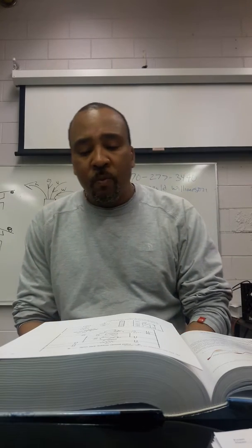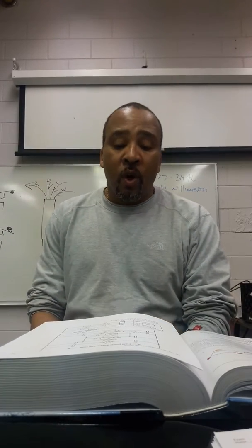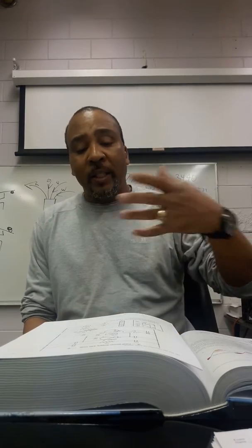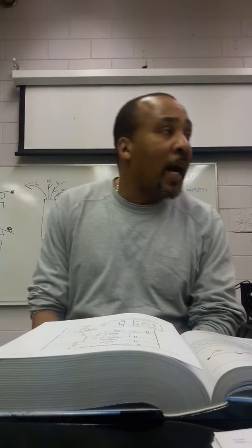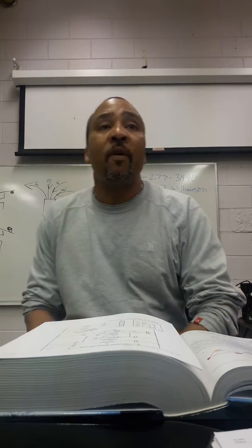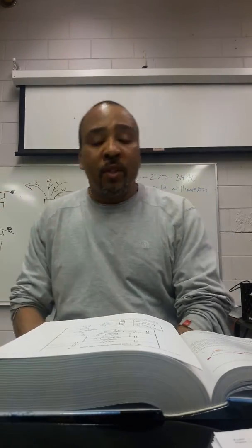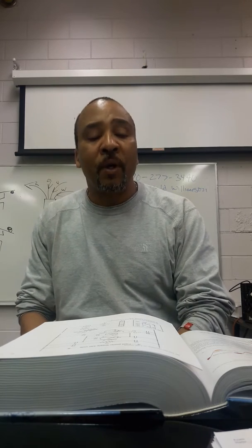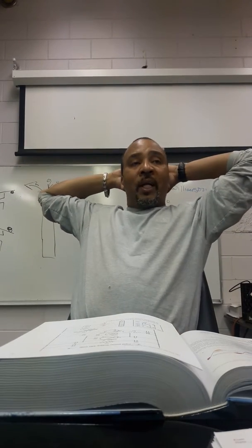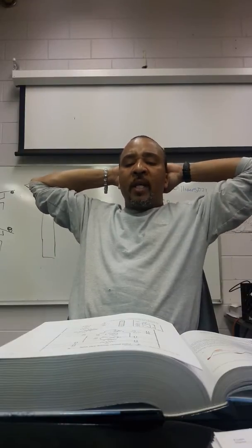So I'm going to take the thermostat off. That's my main control. Or I'm going to go to this terminal block, if it is a terminal block I can get to and is easily accessible, because I can do the same thing. Whatever one is the easiest to access is what I'm going to do. If I have to take my thermostat loose with screws, then I'm going to try to do it from the furnace itself. I'm going to go down to the terminal block and get a jumper wire with clips, and I am going to clip between R and G.